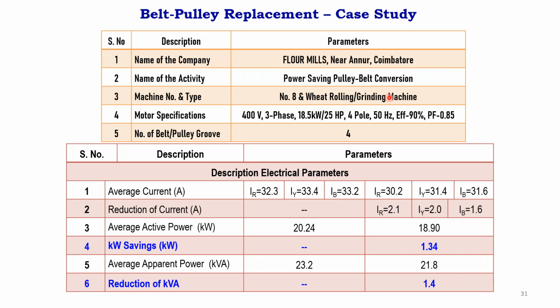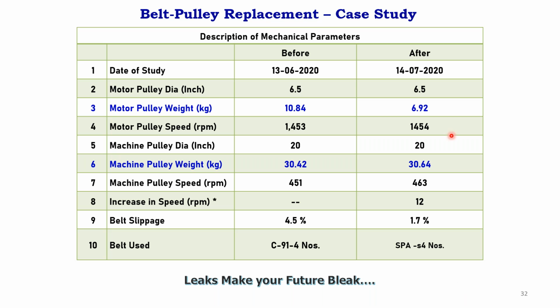This company has around 35 motors of the same capacity for the wheat rolling application, and similarly motors of different capacities, starting from 3.7 kilowatt to a maximum of 37.5 kilowatt. Most of the motors are belt driven, so we recommended this concept to the company. Of course, this is the available value before, and this is the available value after.